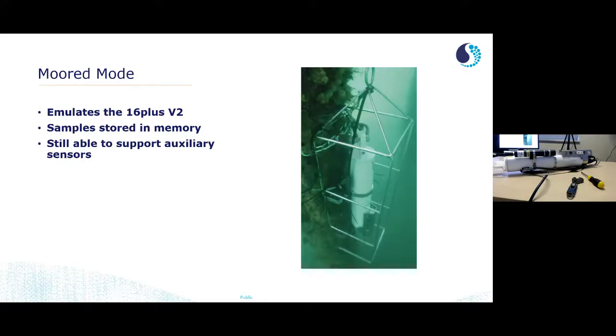Additionally, as mentioned before, this can be configured to work in moored mode. When set up like that, it emulates the 16 plus V2. You can deploy it with real-time output or store the samples in memory, same as the profiling version. You're still able to support auxiliary sensors, provide power for them, and collect the data, saving it in memory or sending it in real time. Word of warning: not every auxiliary sensor is made for both profiling and moored applications. For example, the SBE 18 pH sensor isn't really made for moored applications, just designed for profiling. So if you have an 18 pH sensor installed on your 19 plus V2 and reconfigure it for moored mode, don't expect good pH data for much longer than about half a day. Just FYI.